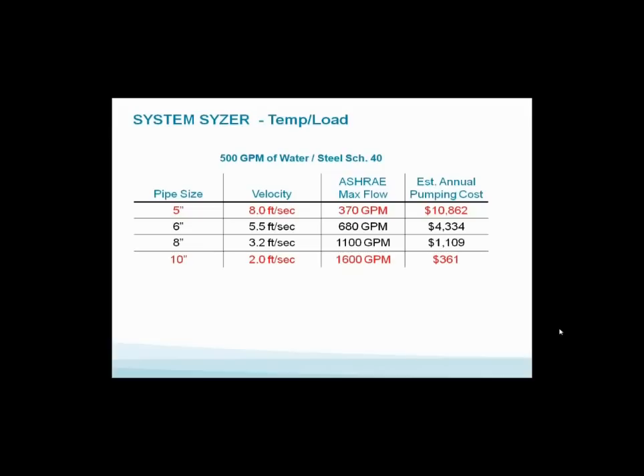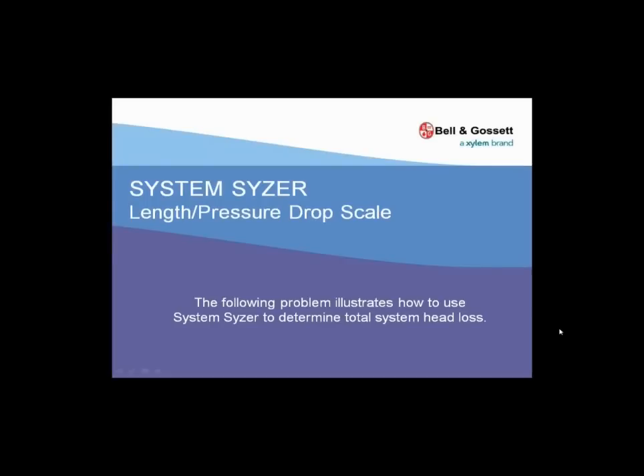It's real simple. We picked a six-inch pipe at five and a half feet per second, max allowable ASHRAE flow rate 680 GPM. We've got an estimated cost of $4,334 per year. Look what happens if I cut the pipe from six to five - I doubled the operating cost. Going from six-inch pipe to five, one pipe size reduction, I doubled the annual pumping cost. That's pretty important, and the system sizer will show you that.